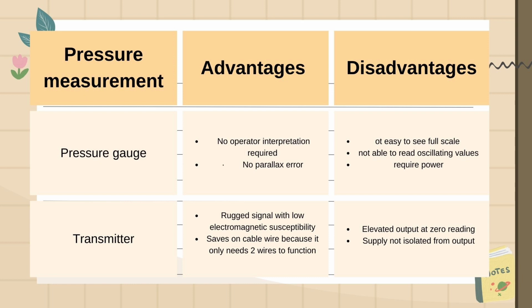Lastly is the transmitter. Advantages for the transmitter are a robust signal with low electromagnetic sensitivity, and it saves on cable wire because it only needs two wires to function. Disadvantages are elevated output at zero reading and supply not isolated from output.